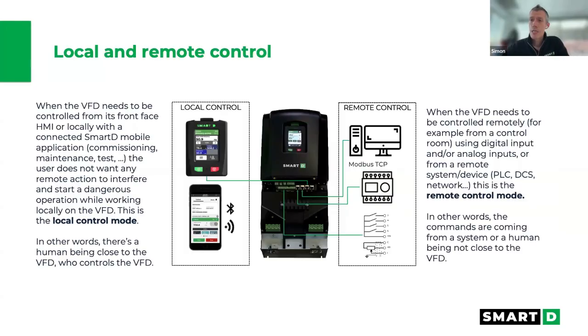We also strongly believe in free, embedded communication protocols. So the drive comes with Modbus TCP and BACnet IP built in. We also have Ethernet IP that will be rolling out very shortly. And all of these are accessible without any additional board. Again, we don't want you to buy external filters. We don't want you to buy external communication boards. We believe everything should be built in.